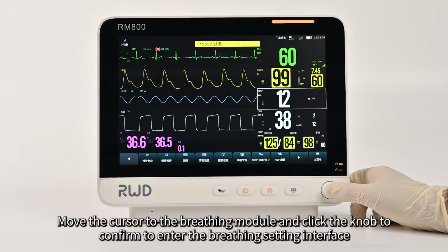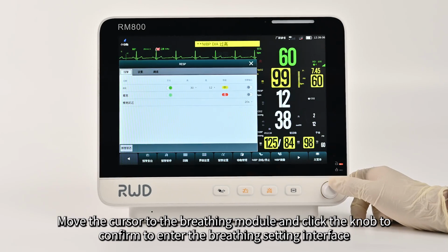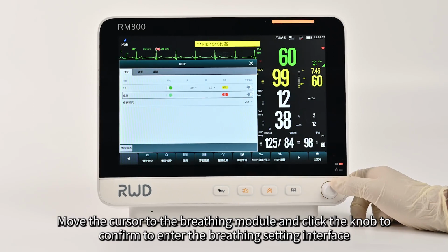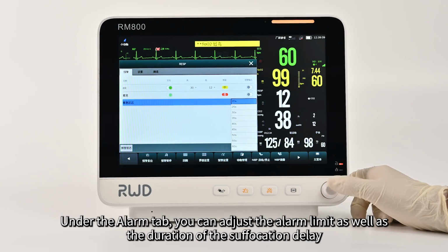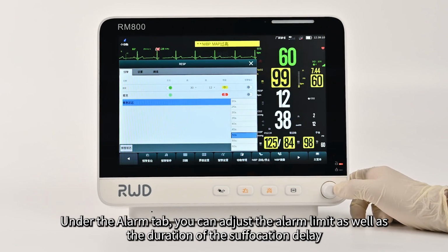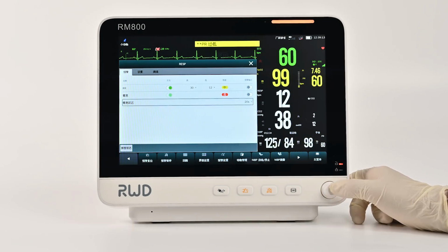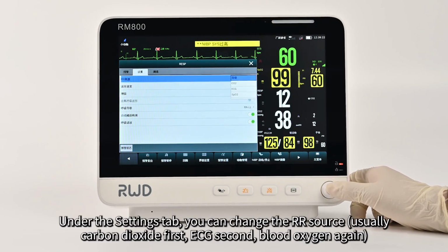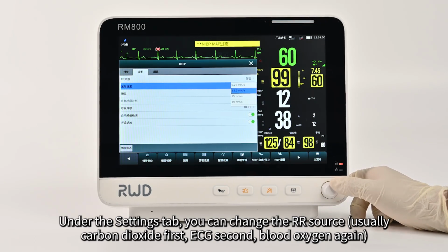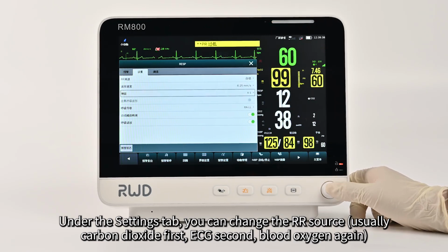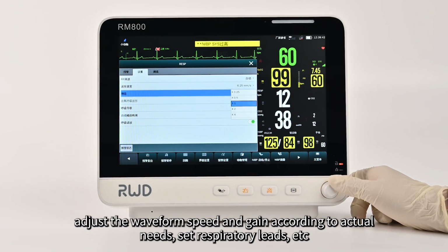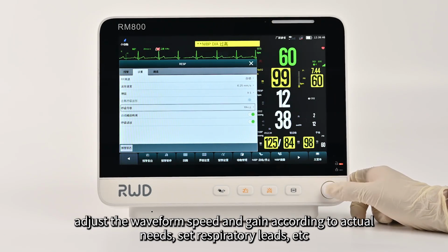Move the cursor to the breathing module and click the knob to confirm to enter the breathing setting interface. Under the Alarm tab, you can adjust the alarm limit as well as the duration of the suffocation delay. Under the Settings tab, you can change the RR source, usually carbon dioxide first, ECG second, blood oxygen third. Adjust the waveform speed and gain according to actual needs, set respiratory leads, etc.